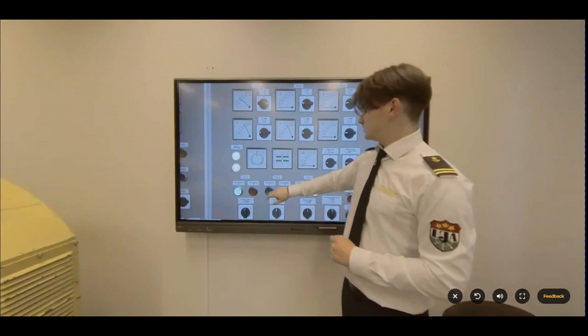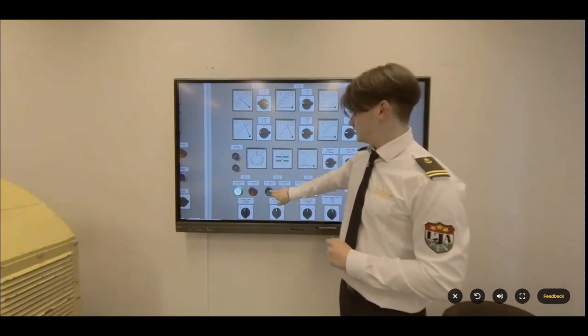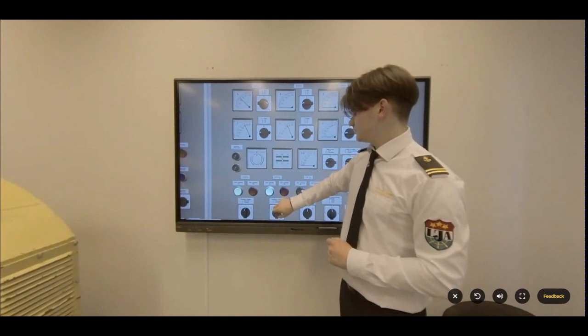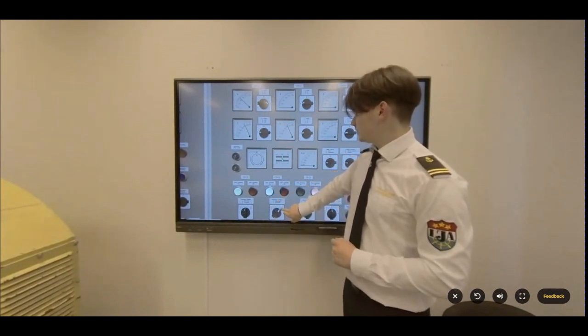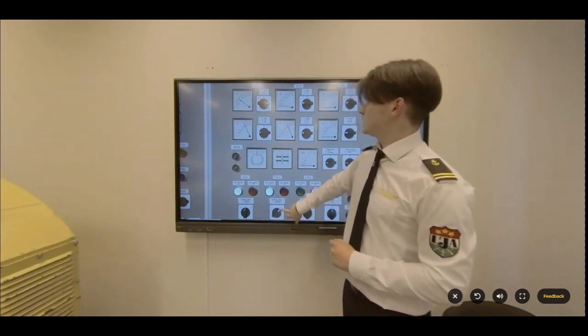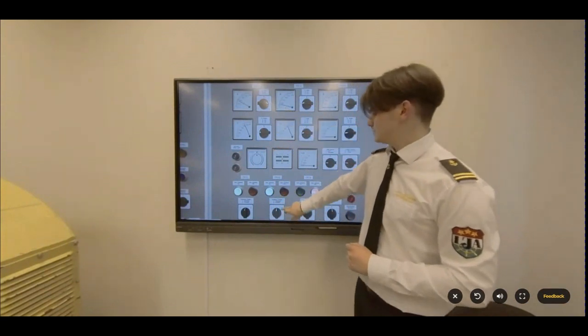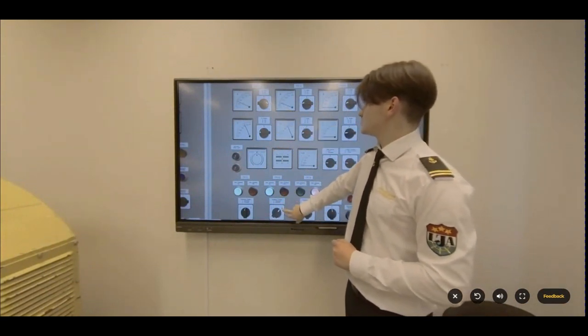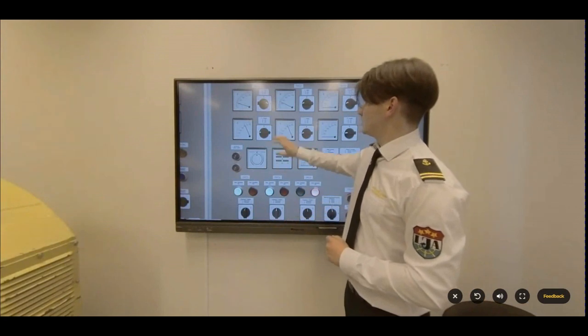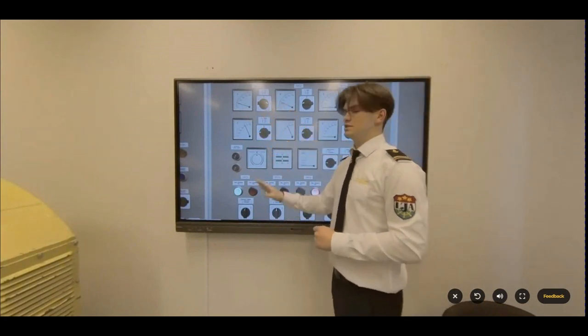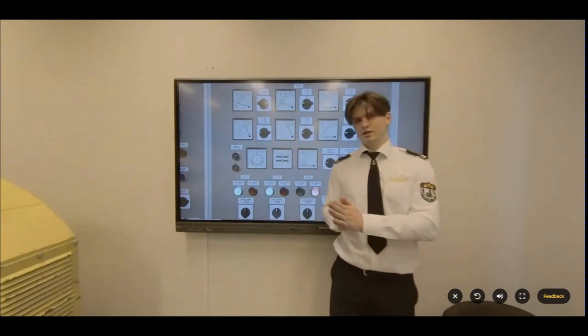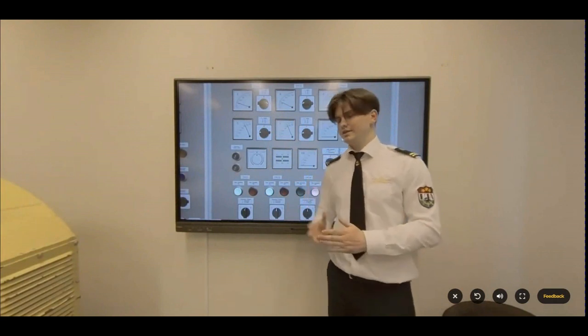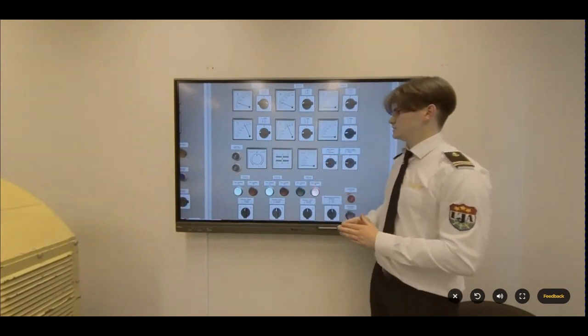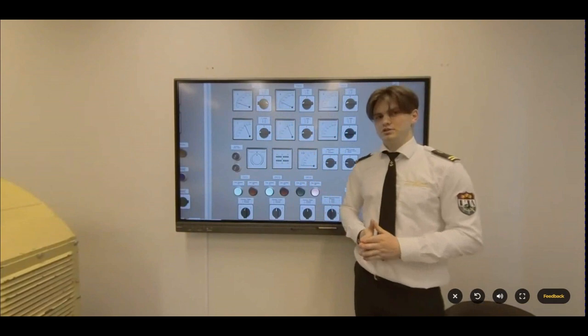Let's do the procedure and wait for the lamp to be in position. Let's press the green one, and now we are increasing revolutions, taking more load on the second generator. Now, approximately, this load is more or less equal for number 1 and number 2 generators. That's the procedure of manual synchronization of two generators.